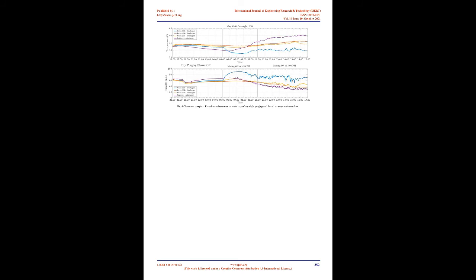For instance, the missing installation of baffles in the student dining facility is one such example of an error that could be fixed later, although it took more than a year to rectify post-construction. Similarly, many louvres were installed with incorrect angles and directions, and several openings were incorrectly provided. The internal surfaces of the misting shafts were also not appropriately finished to meet the high humidity requirements. Some of these surfaces had to be subsequently tiled to avoid the possibility of mold growth.